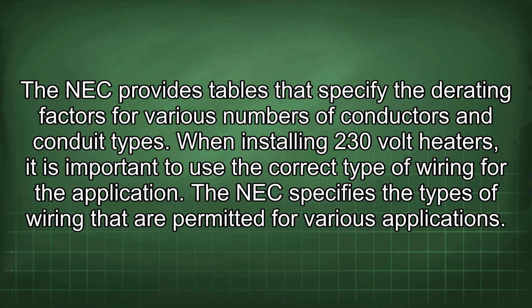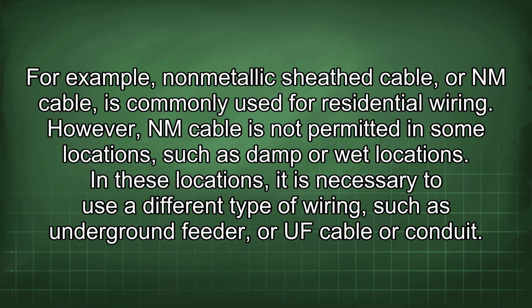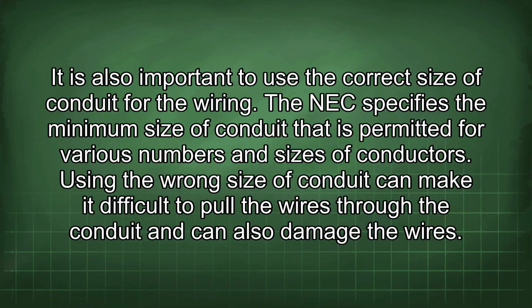When installing 230-volt heaters, it is important to use the correct type of wiring for the application. The NEC specifies the types of wiring that are permitted for various applications. For example, non-metallic sheath cable, or NM cable, is commonly used for residential wiring. However, NM cable is not permitted in some locations, such as damp or wet locations. In these locations, it is necessary to use a different type of wiring, such as underground feeder, or UF cable, or conduit. It is also important to use the correct size of conduit for the wiring. The NEC specifies the minimum size of conduit that is permitted for various numbers and sizes of conductors. Using the wrong size of conduit can make it difficult to pull the wires through the conduit and can also damage the wires.